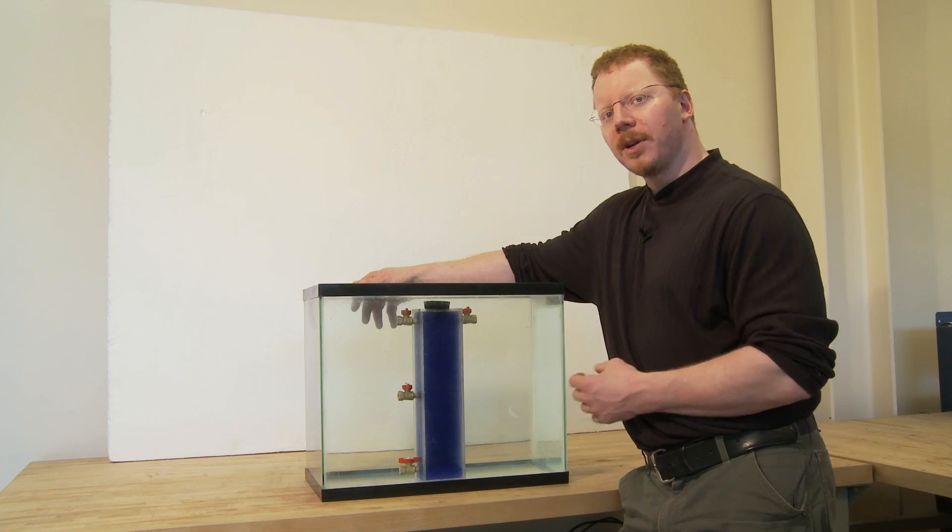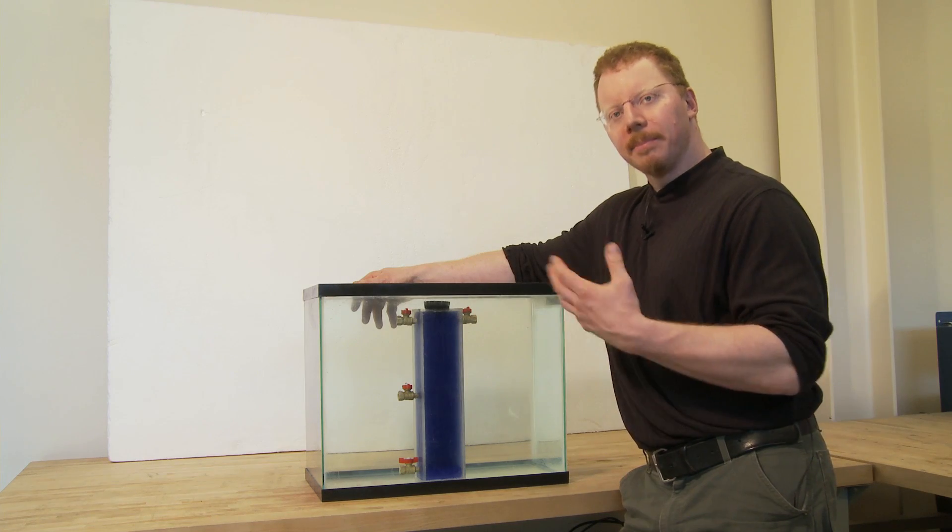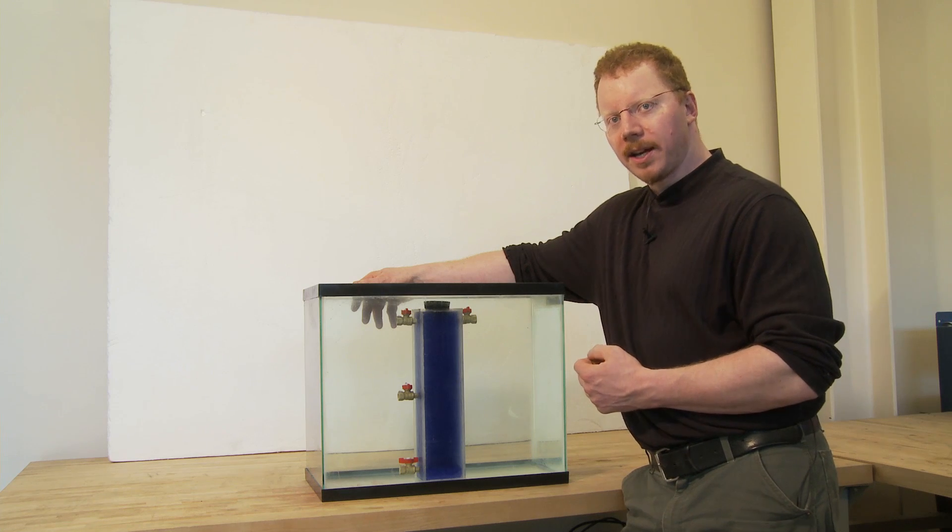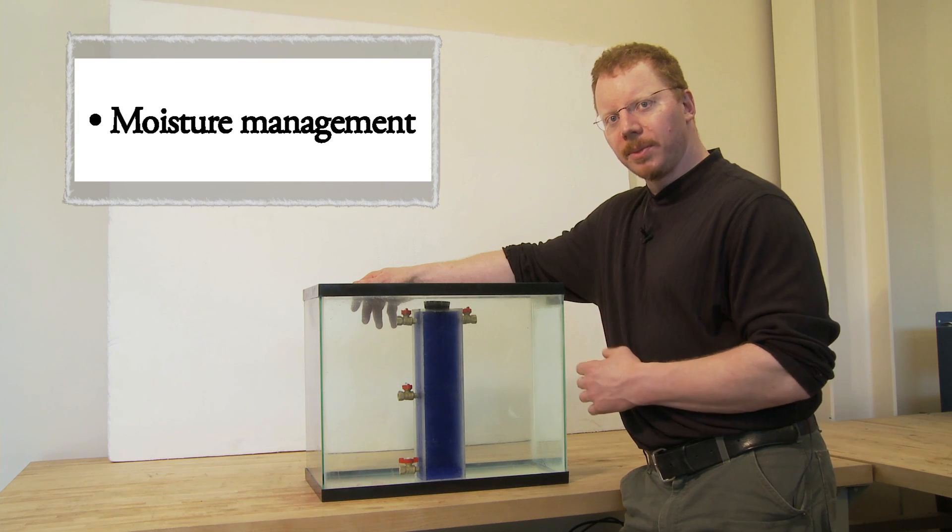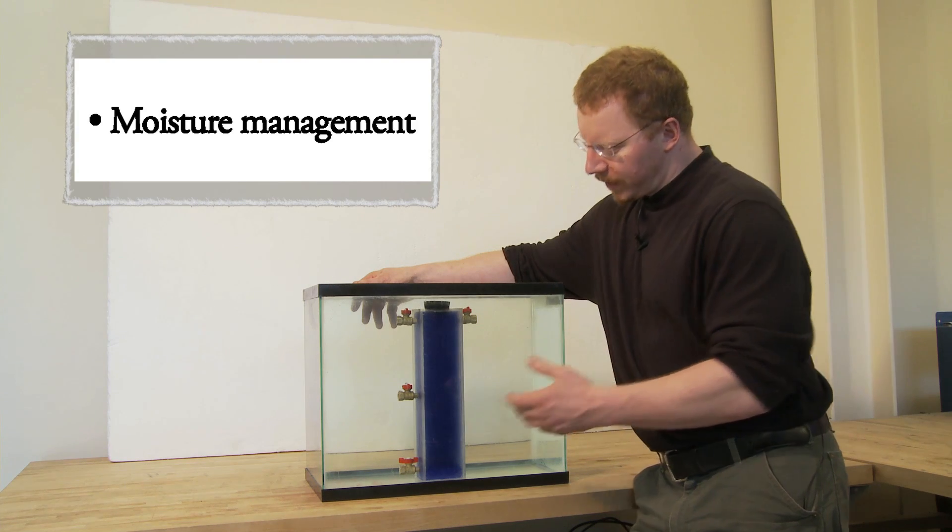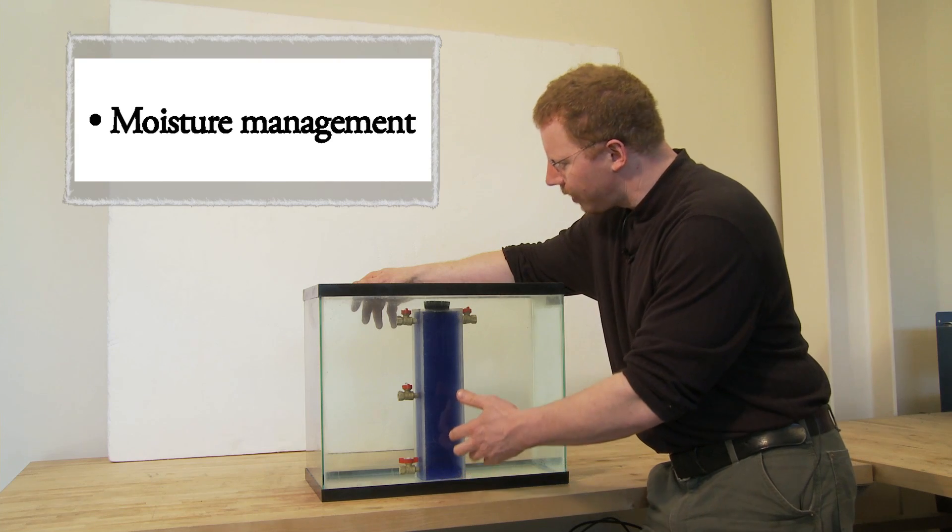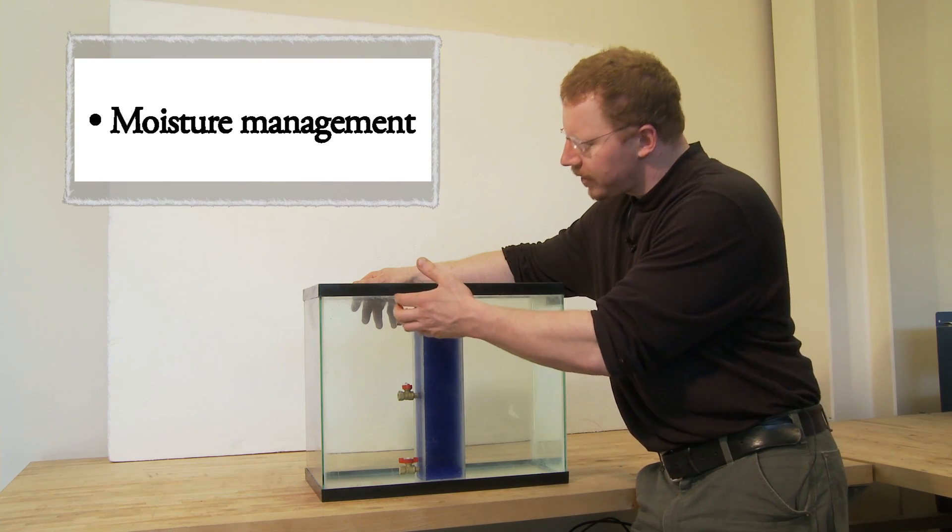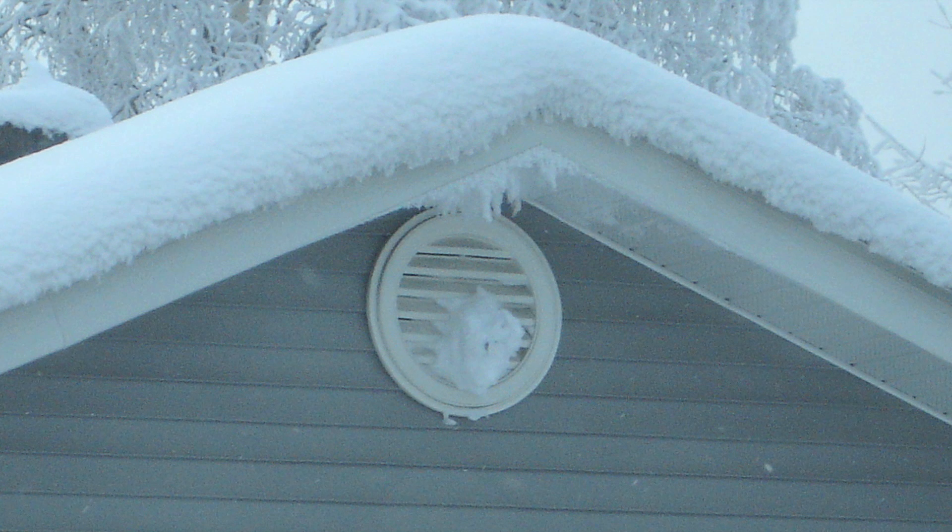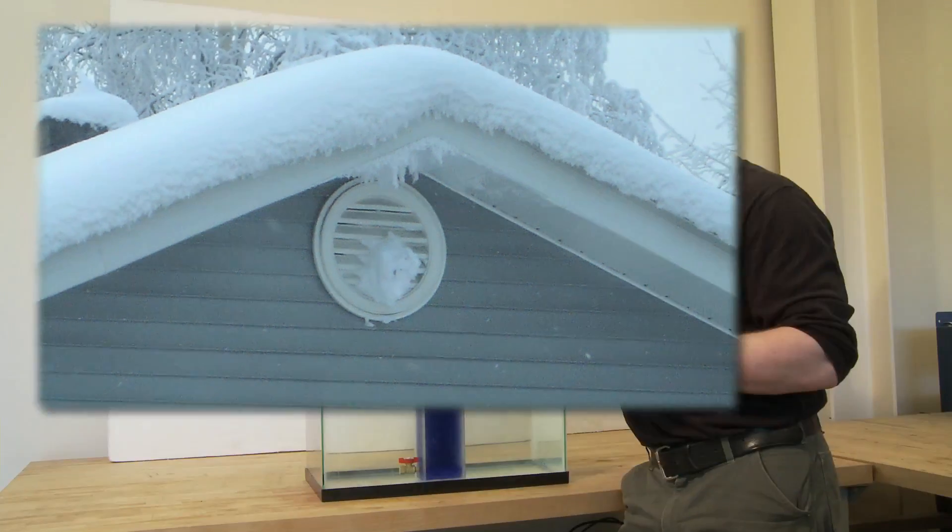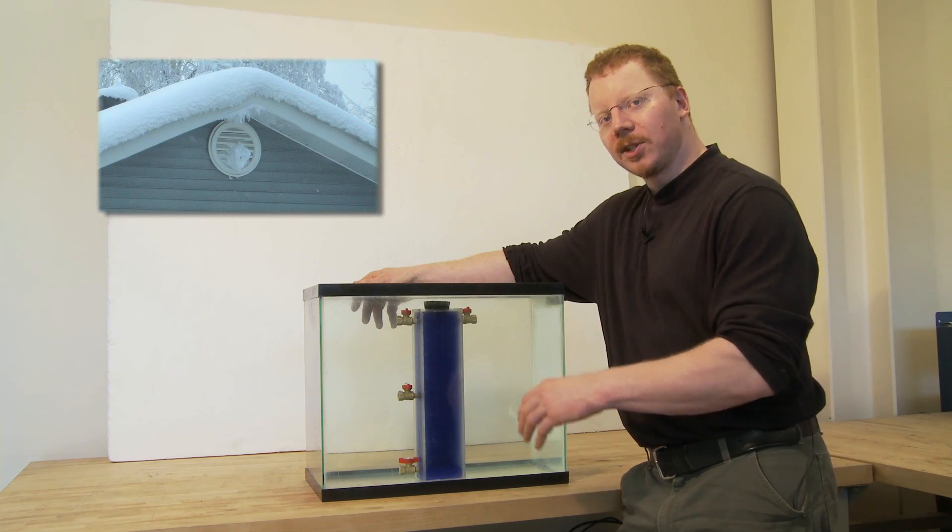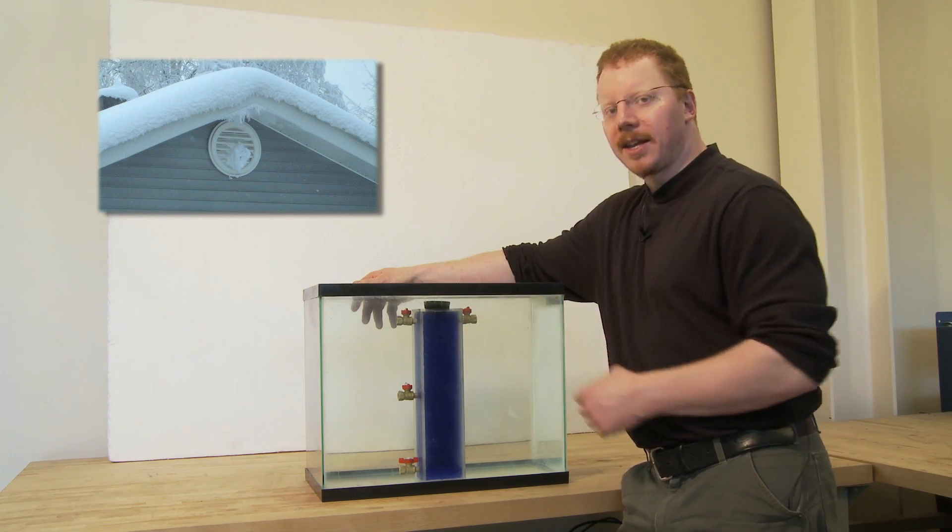All that water vapor that we generate from breathing and showering and cooking and basically living in a house in wintertime, well, that water vapor can travel via air leakage into different parts of the building envelope where we certainly don't want it. And we've demonstrated with stack effect that that hot, buoyant air rises and leaks out up at the top. So if you've ever seen an attic vent in the wintertime with a lot of frost around the outside, well, that's a pretty sure sign that you've got some water vapor traveling via air leakage and stack effect up into your attic. If that water vapor stays up there long enough and becomes trapped, you could have some other problems.